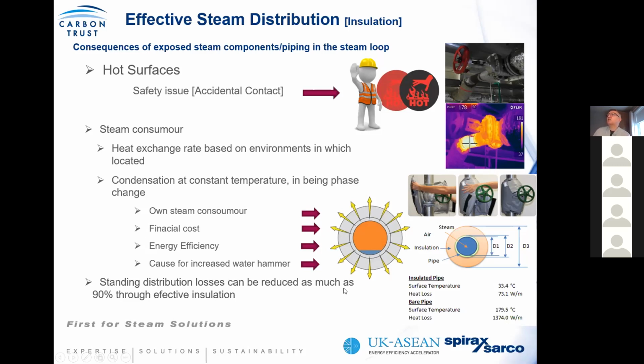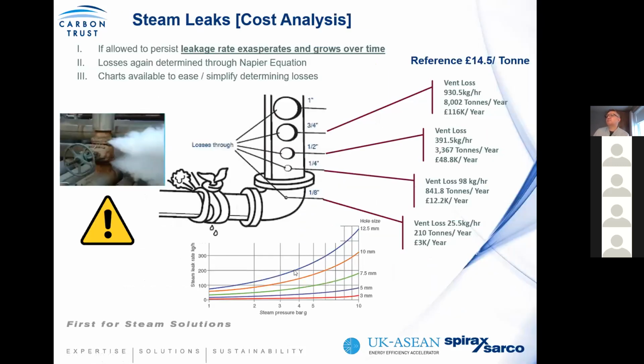So in other words, look at the simple things. Do a survey of your steam system. If you find case examples of this, do it, because the financial impact is that you reduce cost. The efficiency is that it doesn't become a steam consumer, you reduce your steam demand, and you eliminate potential causes of water hammer. If you're looking at something simple like steam leaks, there are sizing charts available that give you a financial indication of the benefit of fixing the leak.